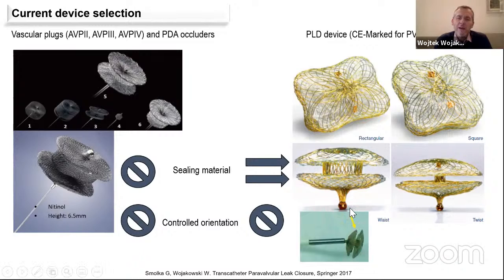For the PLD, it's the mounting on the delivery cable. It's like a ball and the bioptome. So it's not really easy to twist the device. And even if you twist the delivery cable, it doesn't translate one-to-one into the orientation of the plug. So this plug has two markers, which allow you, when you look in the fluoro, to see how it is oriented versus your defect. So if you see the separation of the two dots, you can have some information if they are approaching the PVL towards the short or long axis of the plug.